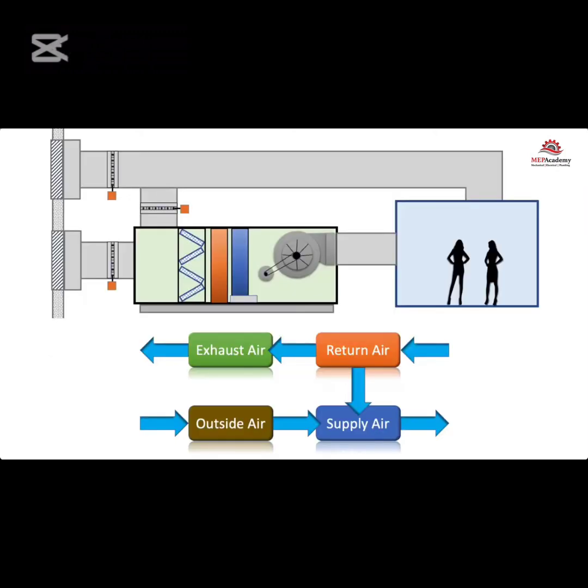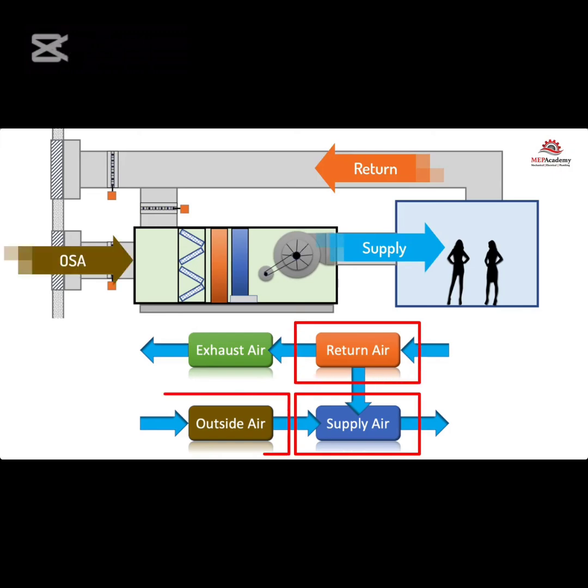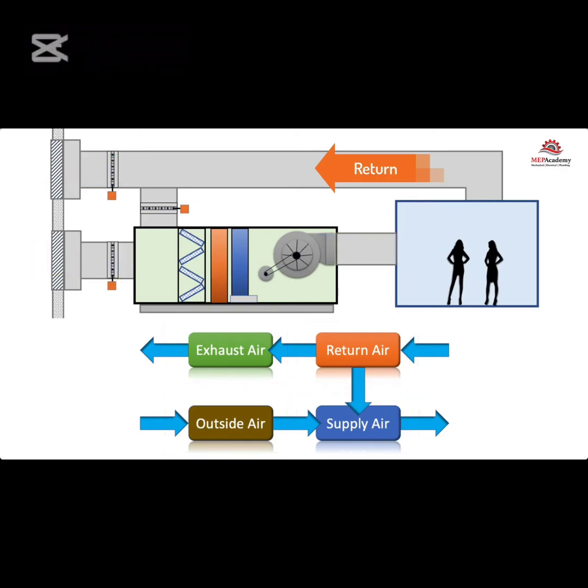An air handler has 4 possible air systems, which include supply air, return air, outside air, and exhaust air. As you can see, the return air system has 2 options. It can return air back to the inlet of the supply, or it can exhaust the air outside. The rest of the air systems only have 1 option, as shown by the directional arrows.